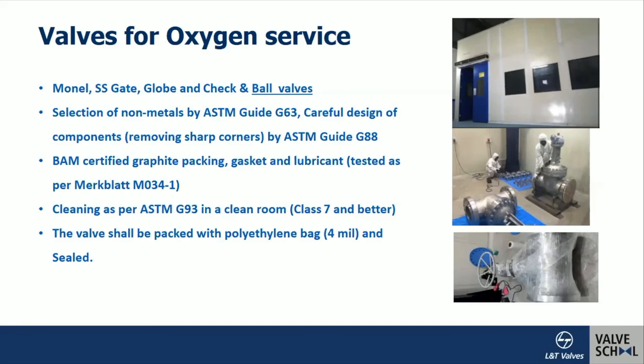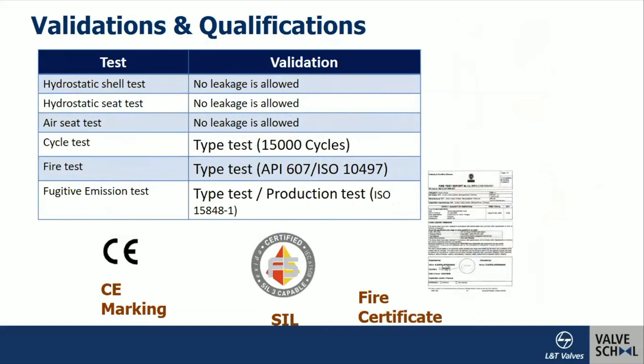Valve qualification includes hydrostatic shell testing with demineralized water (chloride content less than 50 ppm), hydrostatic seat test, and pneumatic seat test with compressed air. For gas applications, customers can request additional gas testing. Prototype qualification involves a cycle test — normally 15,000 cycles — with some manufacturers performing up to 50,000 cycles for high-frequency applications. Fire-safe testing is performed as per API 607 and ISO 10497.